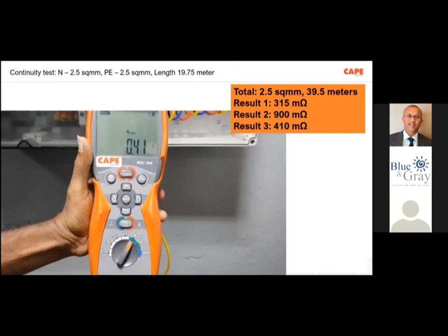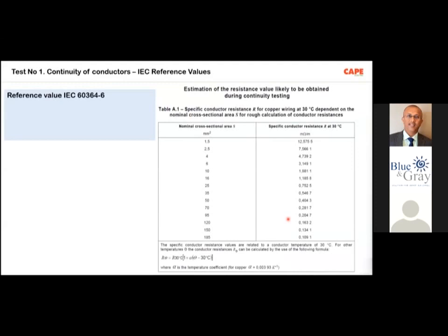What you should do is, first understand what kind of wire it is, what the size of the wire is, and what the length of the wire is. Then you get a good and very accurate meter and test the continuity resistance of that particular wire. Then you go to the reference value in the IEC standard, IEC 60364, or the upcoming National Electrical Code. For 2.5 square millimeter wire, the value is 7.56 milliohm per meter. So for 39.5 meters, approximately we are supposed to get 299 milliohm, whereas our meter has shown 315 milliohm.